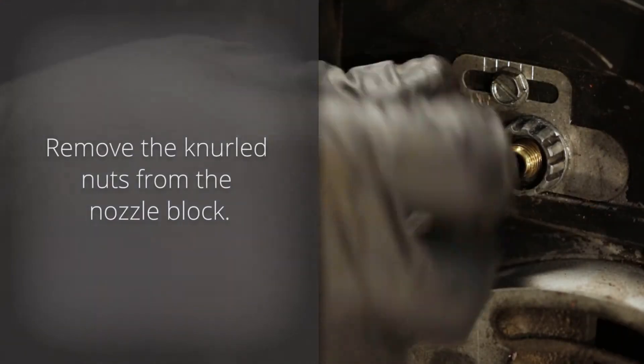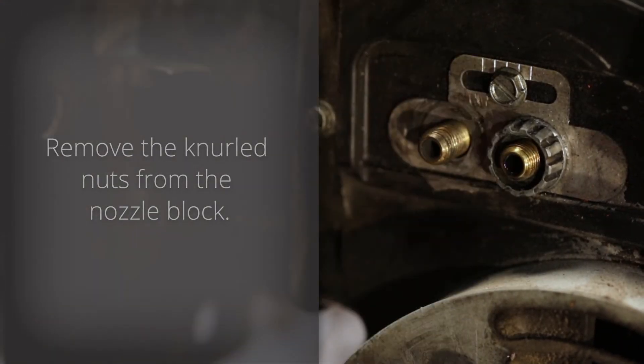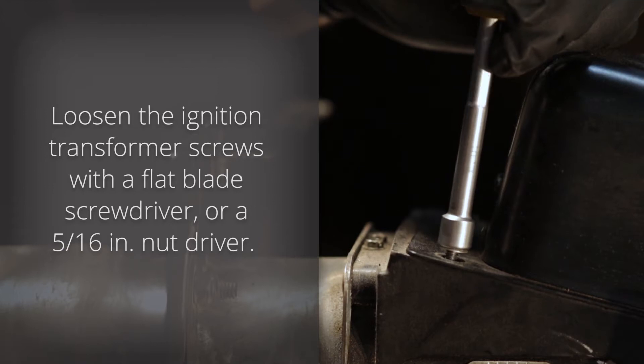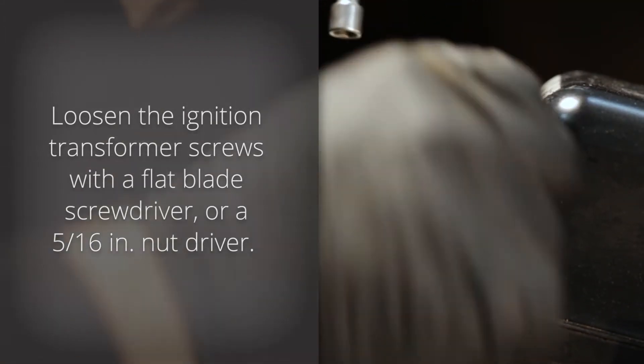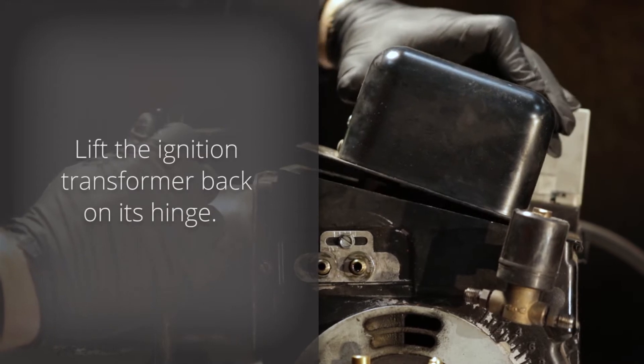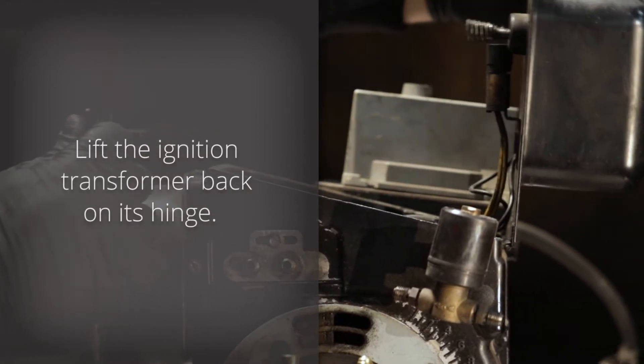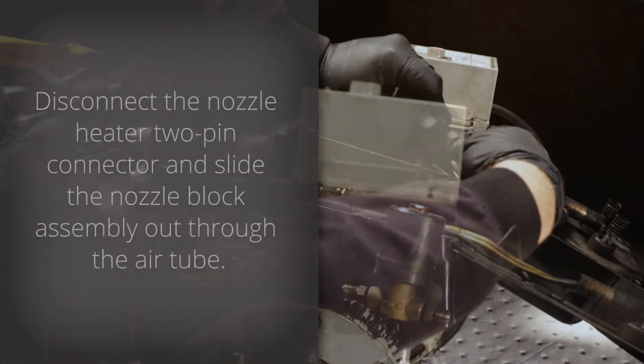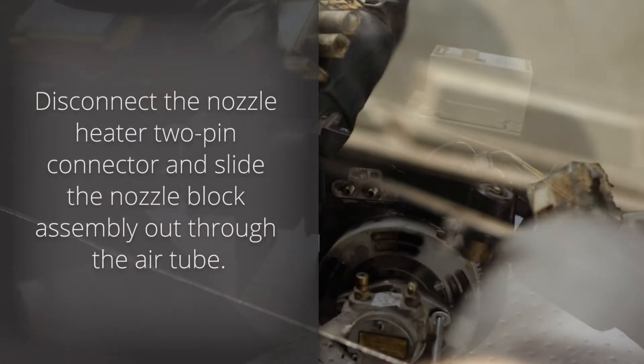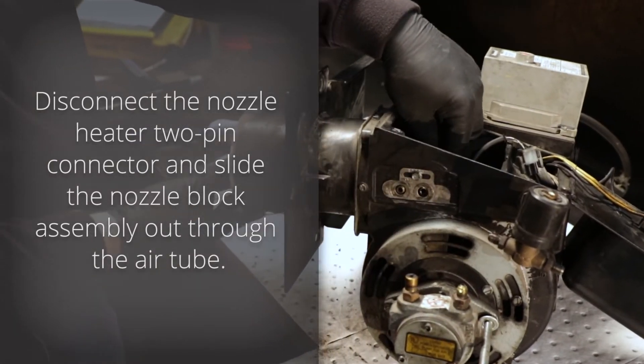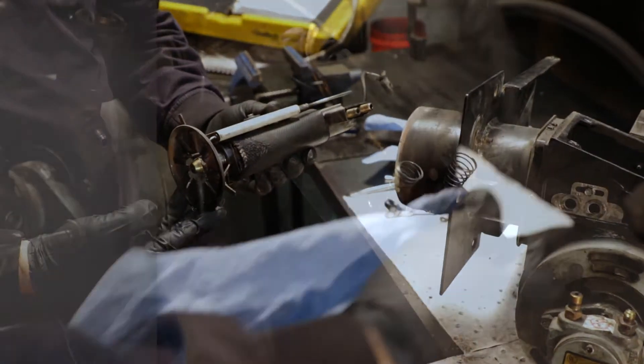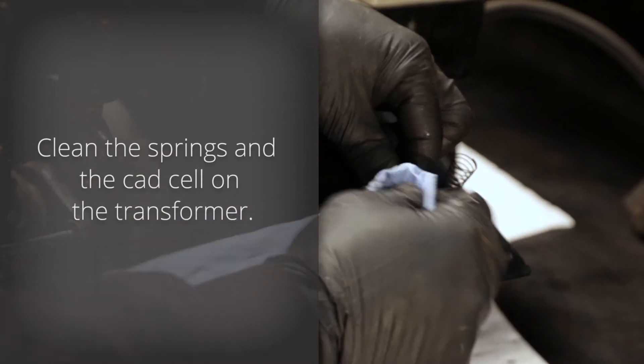Remove the knurled nuts from the nozzle block. Loosen the ignition transformer screws with a flat blade screwdriver or a 5-16th inch nut driver. Lift the ignition transformer back on its hinge. Disconnect the nozzle heater 2-pin connector and slide the nozzle block assembly out through the air tube. Clean the springs and the CAD cell on the transformer.